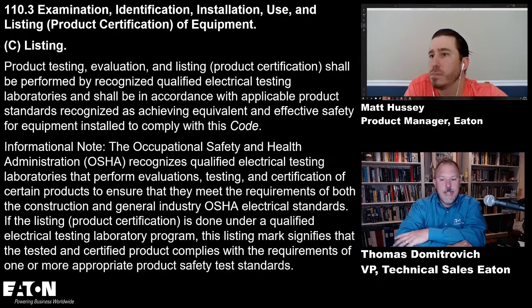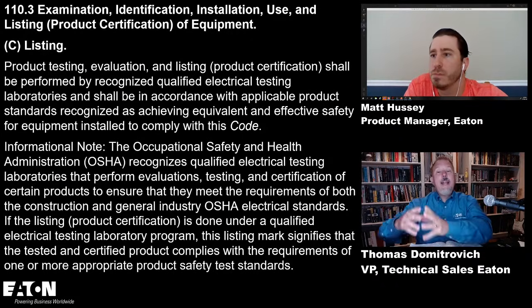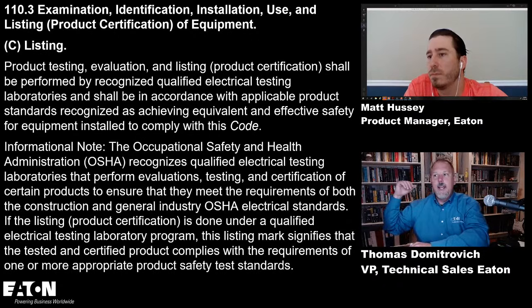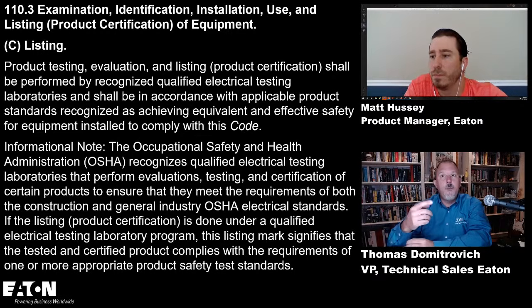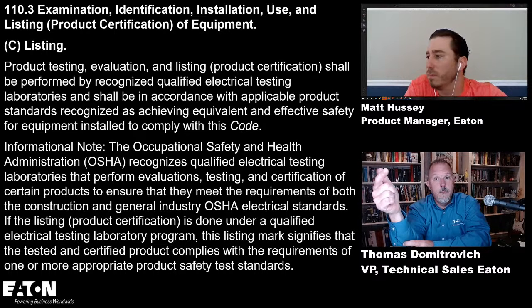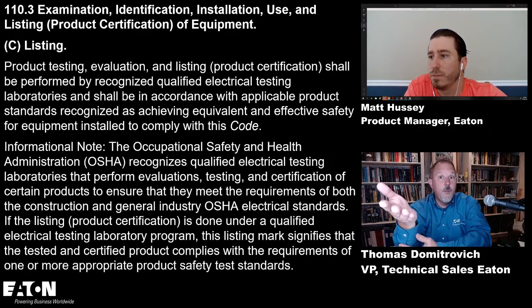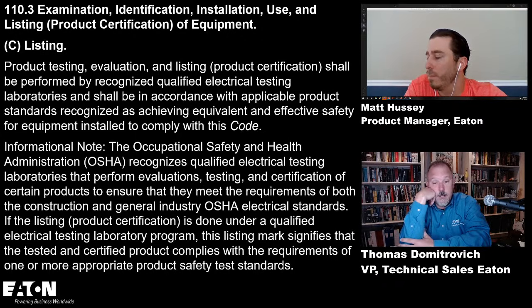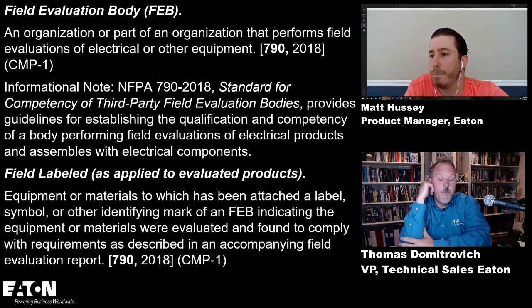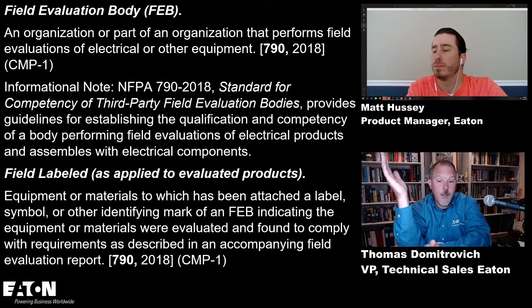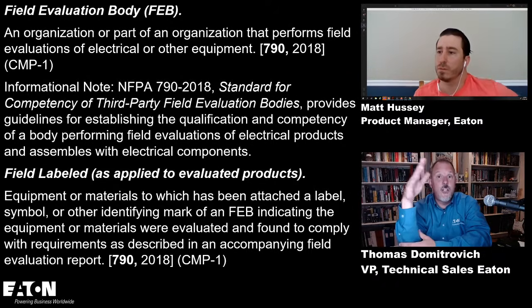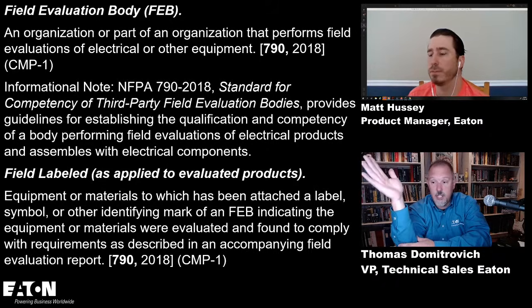So where our discussion is, if you're going to make this change in the field, you're going to take an MCC and extend it, even if I bought a new one, I probably should get somebody to look at that installation, like some sort of nationally recognized testing laboratory. Or if I bought one from you, the manufacturer, would I need to get a field evaluation? Correct. So you would be employing some field evaluation body to come out and take a look at that installation as you're modifying it in the field, because it's not as it was when it shipped.